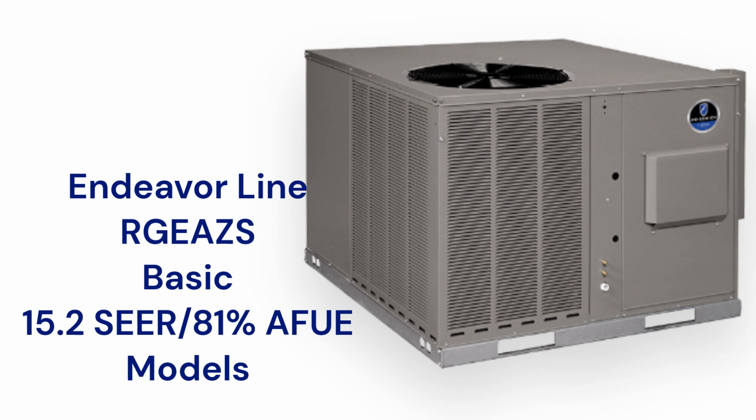All of the units use direct spark ignition, which is not as reliable as brands that use hot surface ignition. The guarantee on the units is only average when compared to other brands, as it does not have a unit replacement guarantee in case of compressor or heat exchanger failure.